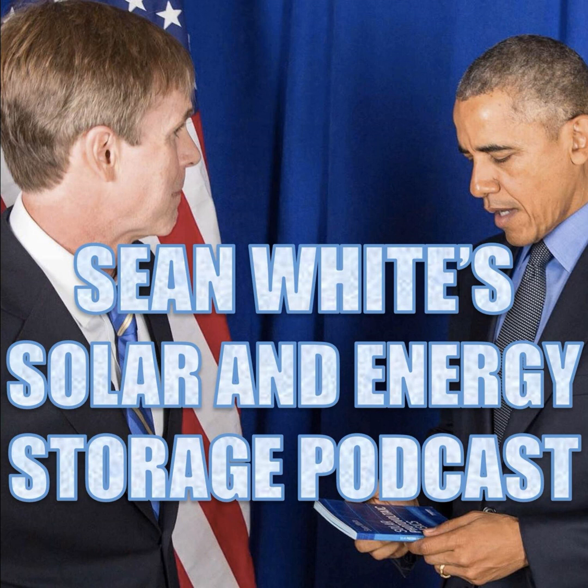So some of you may remember SunPower back 10 years ago, their modules had to be positively grounded instead of negatively grounded. And one of the things that they would do with their systems is they would have a nighttime depolarizer, they called it, that would basically connect the system at night to the positive to ground. There's a variety of reasons for doing that, and they would often do that through a resistor and things like that. So that's an example. And there are other types of resistively grounded systems in healthcare and other areas in the AC world that use an impedance ground. If it's an AC system, we're going to call it an impedance ground, whereas if it's DC, we'd call it a resistance ground. But again, those are very rare. That would be a rare occurrence of an awfully rare thing to start with.